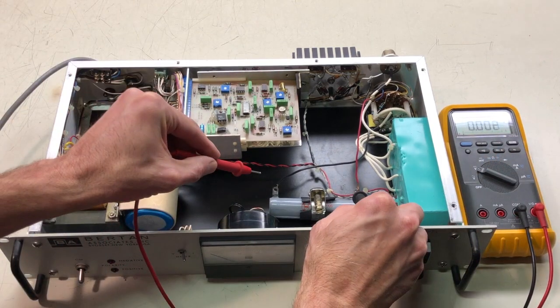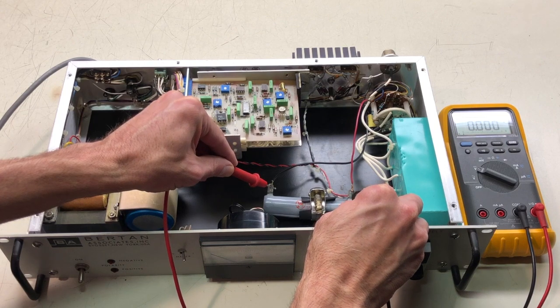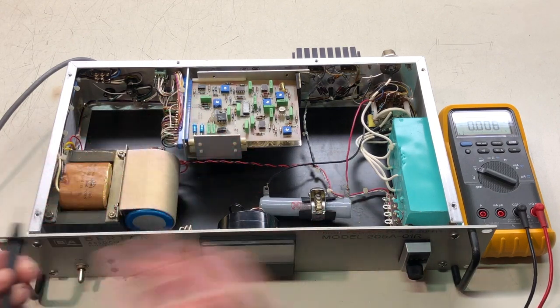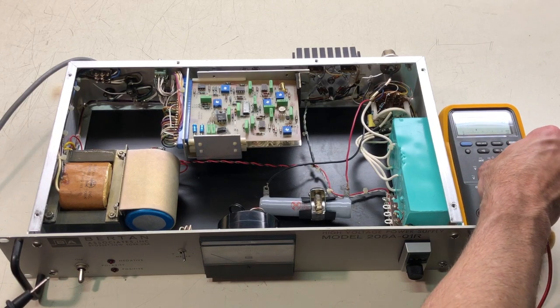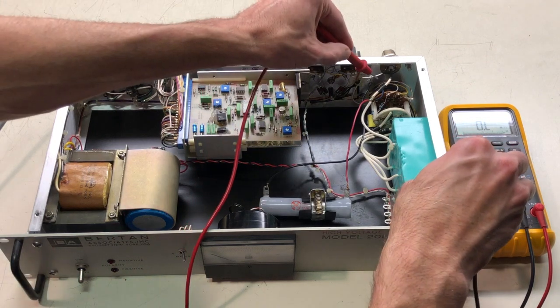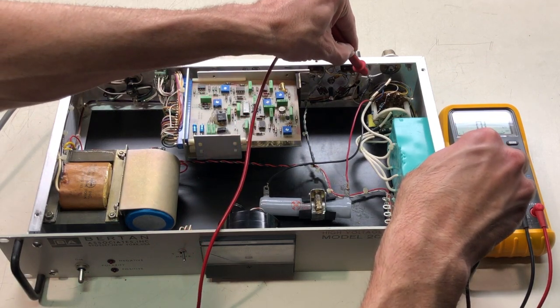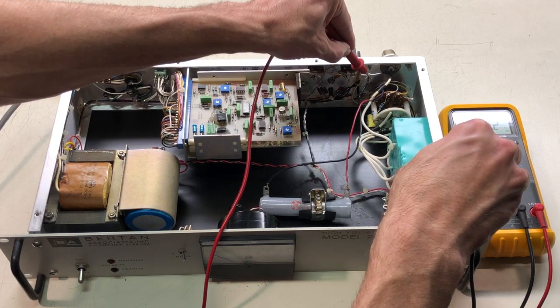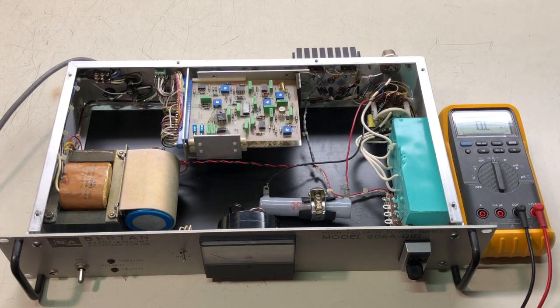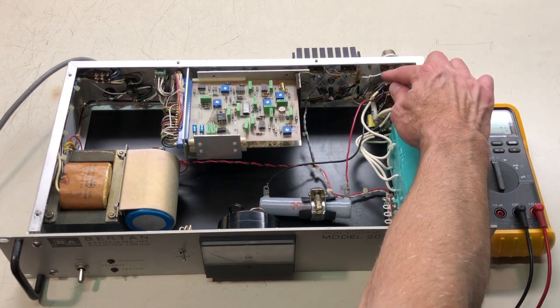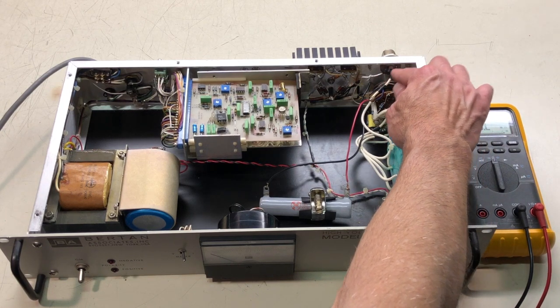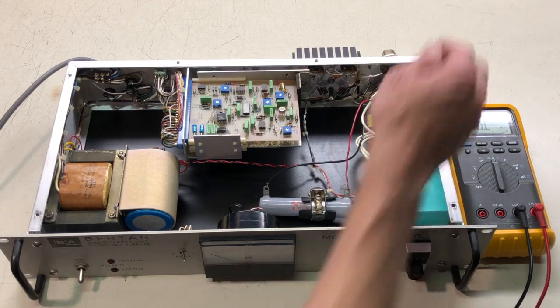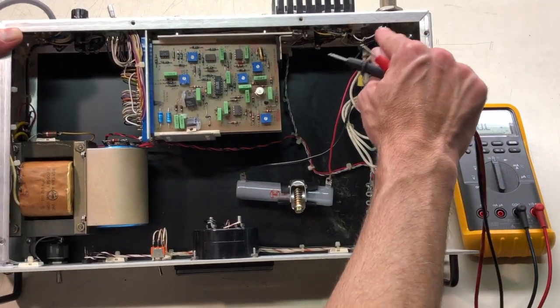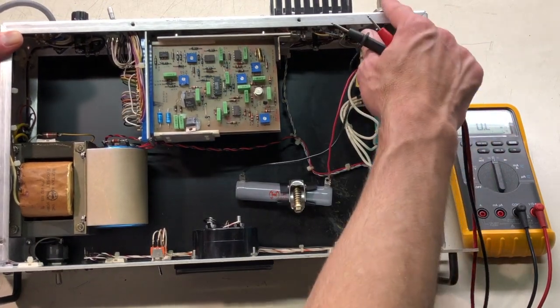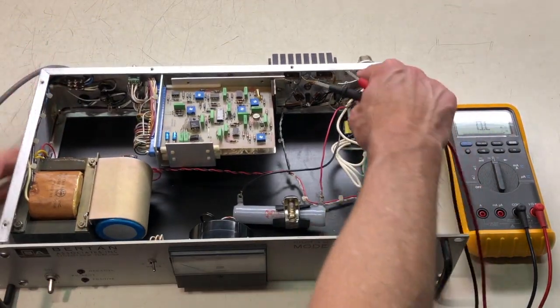Let's make sure we've got no output voltage here. Nope, we're all good on that. From chassis to this ground connection here. Yeah, it's a direct connection. So on this output connector, the ground connection is on an inside sort of ring. It's not on this threaded output back here, this nut, this bulkhead connector. The ground connection is actually on an inside connection, like a triaxial sort of connector, but that wire actually goes right to chassis ground.